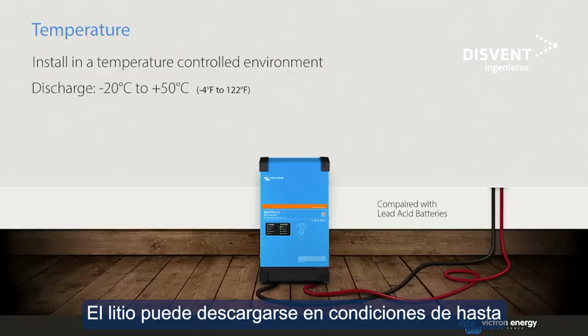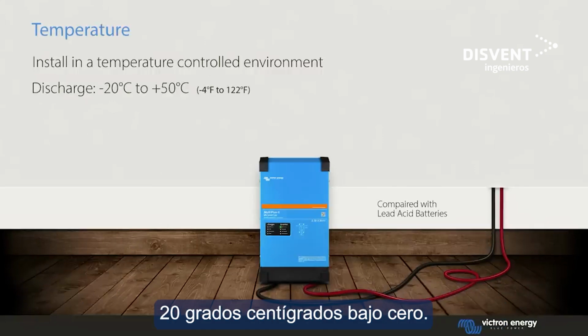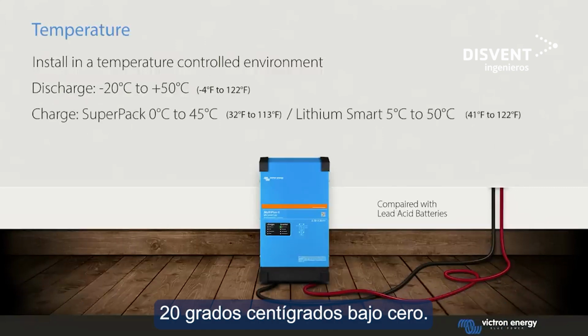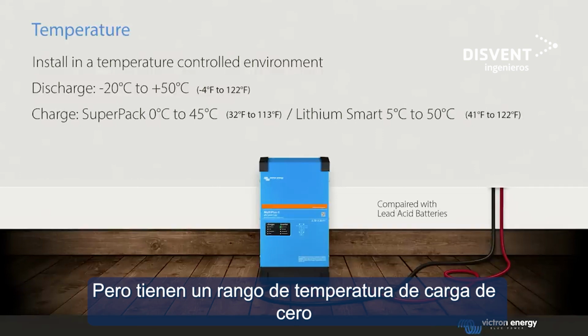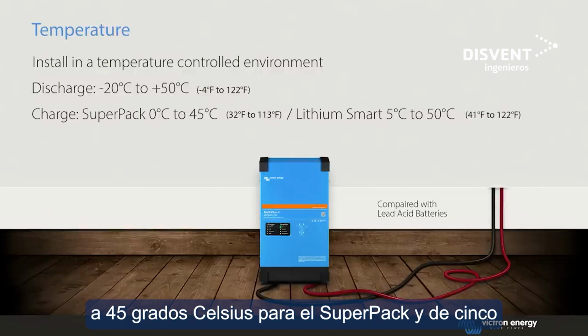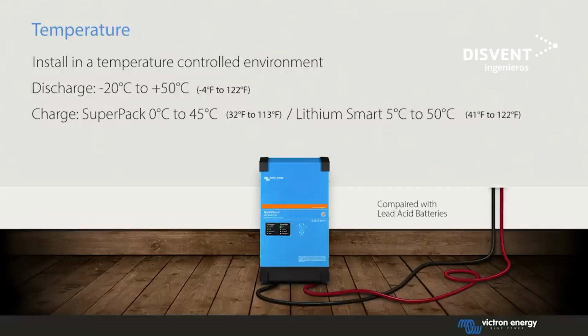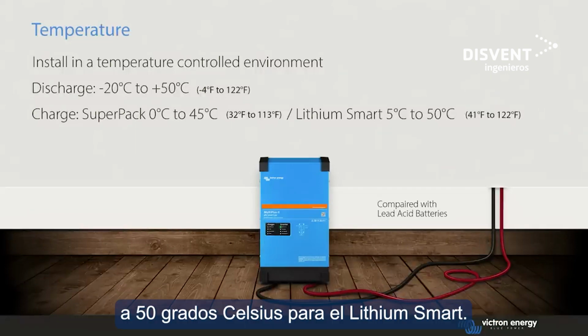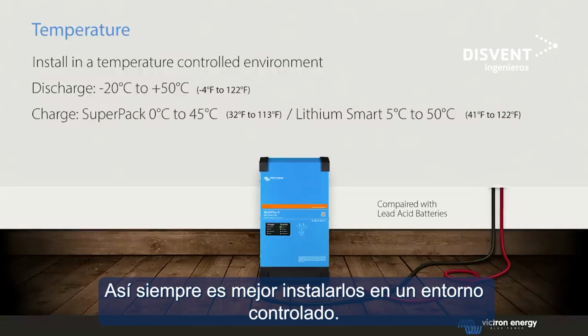Lithium can be discharged in conditions down to minus 20 degrees Celsius, but they have a charge temperature range of 0 to 45 degrees Celsius for the SuperPack, and 5 to 50 degrees Celsius for the Lithium Smart. So inside in a controlled environment is always better.